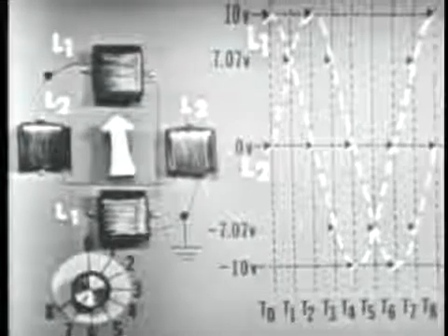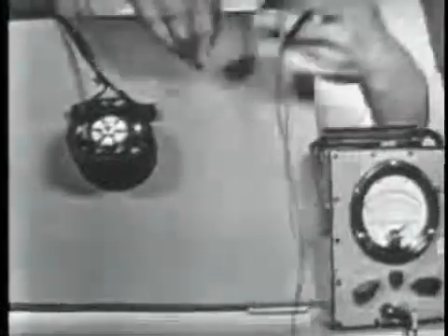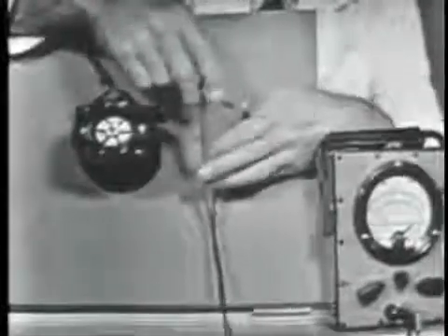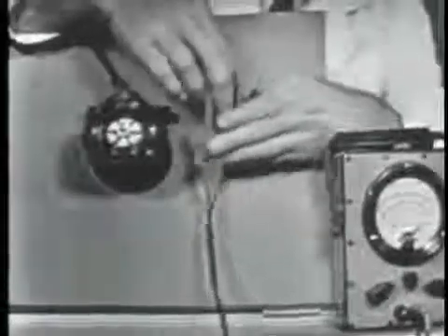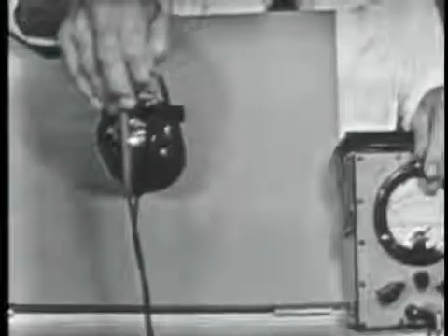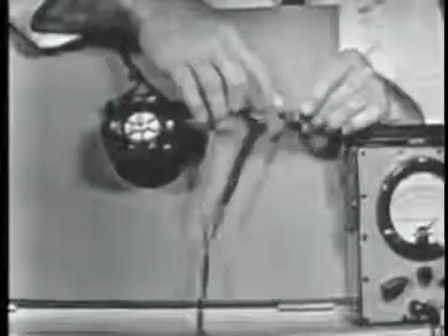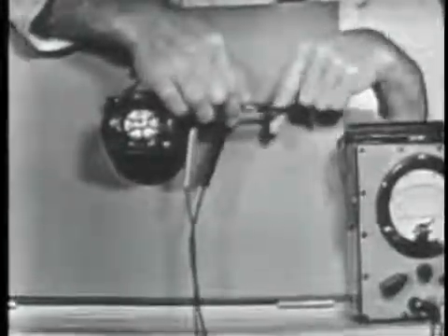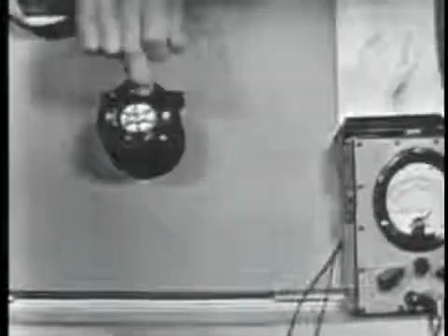Right. Now, I'll take item 4. All right. Help us out. All right. Item 4, the rotor acts like a magnet. Well, it actually becomes an electromagnet. Right. And follows a rotating magnetic field because of induction. Okay, and we proved that with this little loop of wire, the resistor and the PSM6. We put the loop in the field windings, and the PSM6 showed us that we did have a voltage induced into the loop, causing current to flow. Once we had current to flow, we know that the loop had to become magnetized and exhibit a north and a south pole. And once we get it magnetized, it has got to follow the rotating magnetic field.